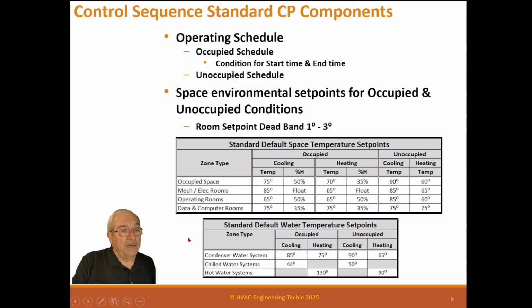Then the other thing here is standard default water temperature set points. Everywhere in these sequences where we talk about set points, enter points or exit points, everything is variable and can be set and limited by an operator. And there are reasons for that. If you get out there in the system, you may discover that your set points are so close you have cycling, so you may spread them a little bit to avoid that cycling. There are things like that that are always adjustable, but they have to make sense and come in the right order. But as far as their width, you can change those.